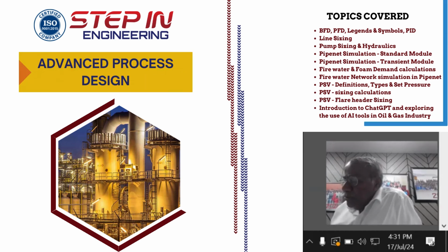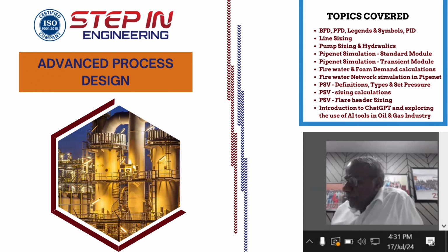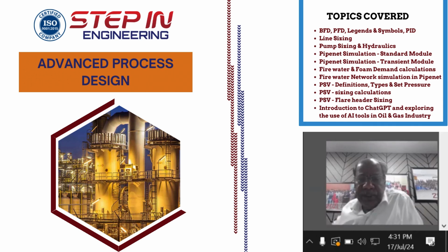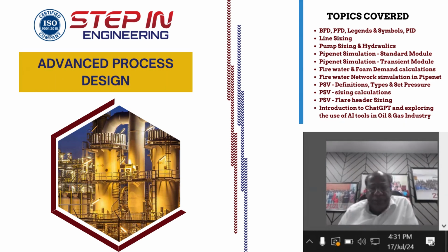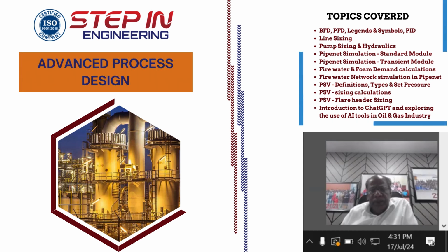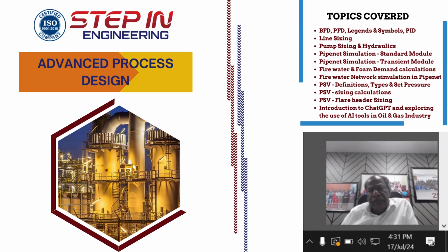Module 10 is going to be based on API 521 and 520. The actual PSV sizing calculation we are going to demonstrate live. Suppose it is a gas phase or a liquid phase, how do you do that? How do you select the design pressure? How do you estimate the orifice size required for the PSV? After I have estimated the orifice size, how do I pick the PSV? With respect to API 526, we will demonstrate how to pick the PSV size from the codes and standards.